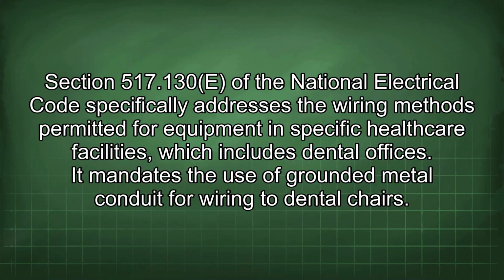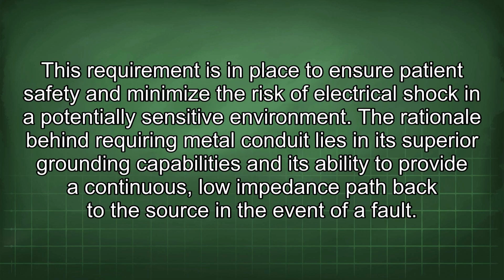Section 517.130 of the National Electrical Code specifically addresses the wiring methods permitted for equipment in specific healthcare facilities, which includes dental offices. It mandates the use of grounded metal conduit for wiring to dental chairs. This requirement is in place to ensure patient safety and minimize the risk of electrical shock in a potentially sensitive environment. The rationale behind requiring metal conduit lies in its superior grounding capabilities and its ability to provide a continuous, low-impedance path back to the source in the event of a fault.